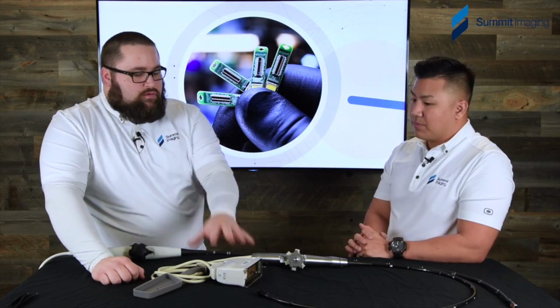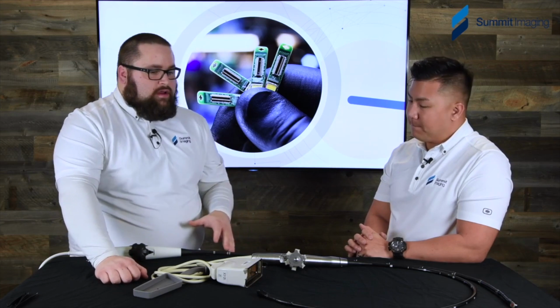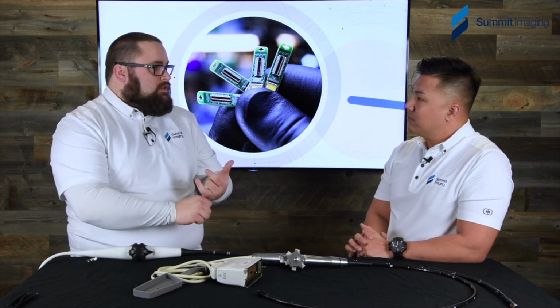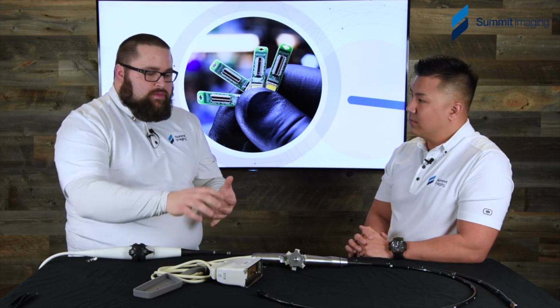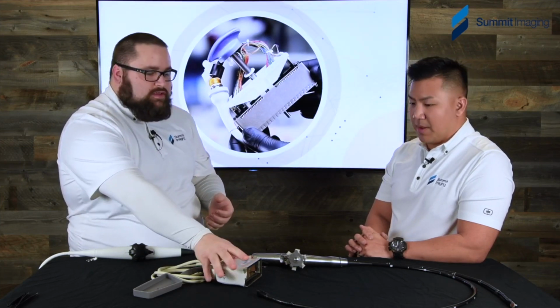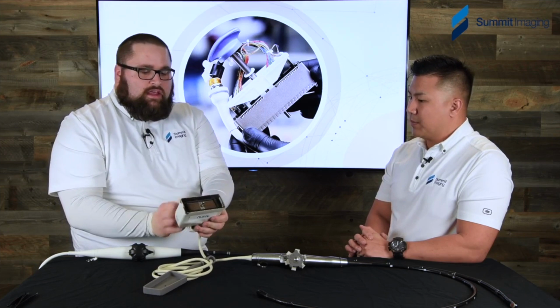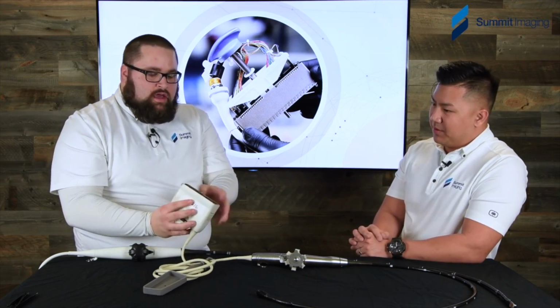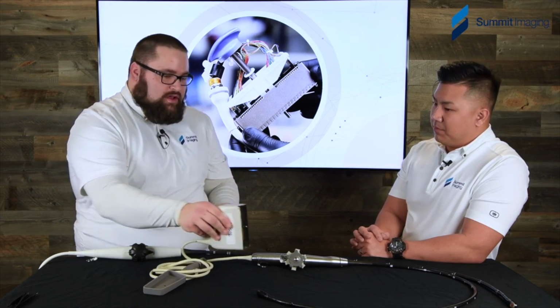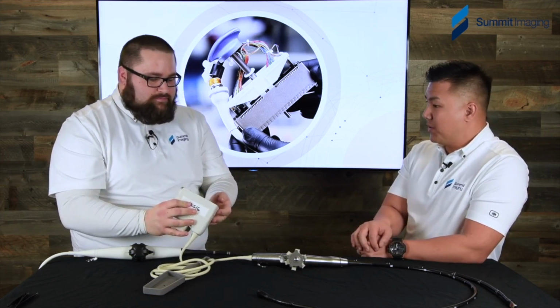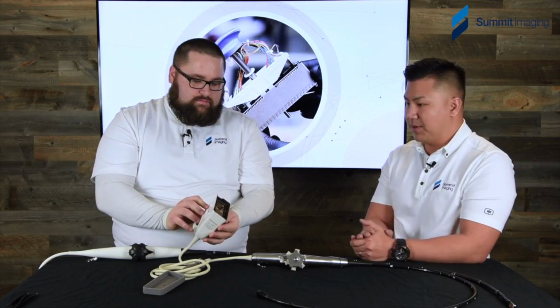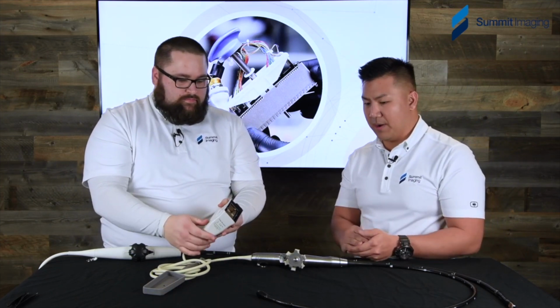Let alone, this is the ground to the machine. So we talked earlier about exposure with the patient to losing the ground, and then the patient becomes the ground. This is where the end of that connection is going to be. So if it's not connected to the system properly, say the locking pin is loose because it's been damaged, or we're missing a nice big chunk out of our solid connection. Yeah, let's chat about that for one second, because we've had some interesting experiences on probes coming in where there was a lack of understanding of how these are built, and then some really odd repairs occurring, and it puts the patient at risk.